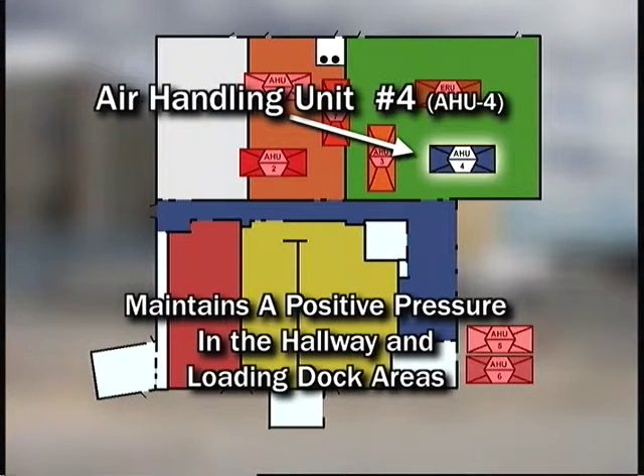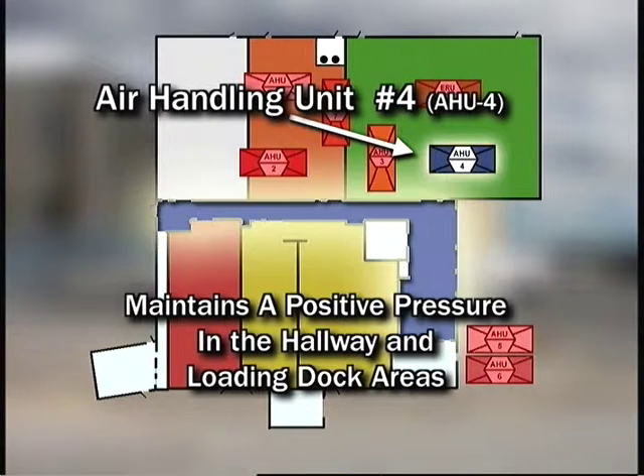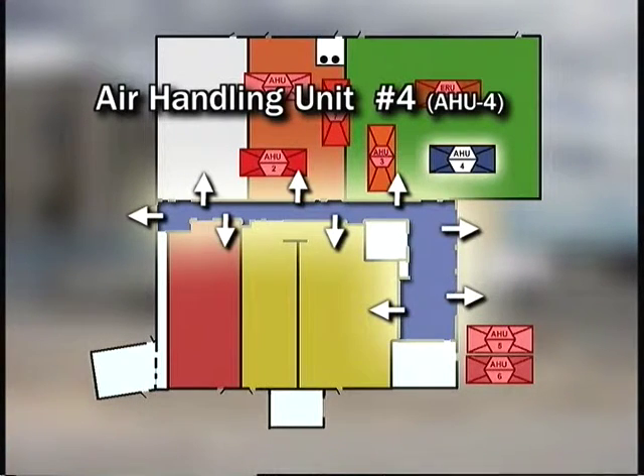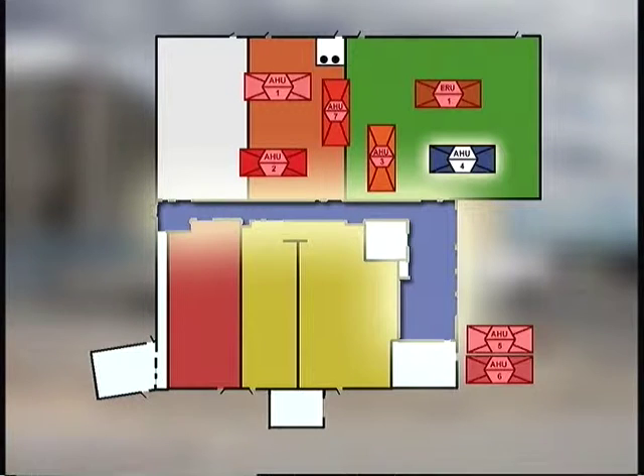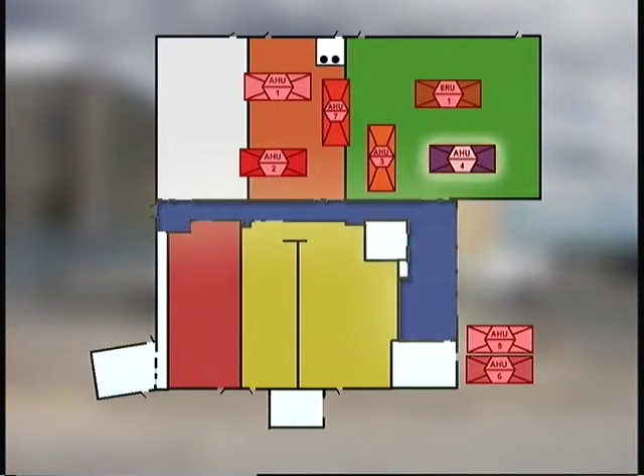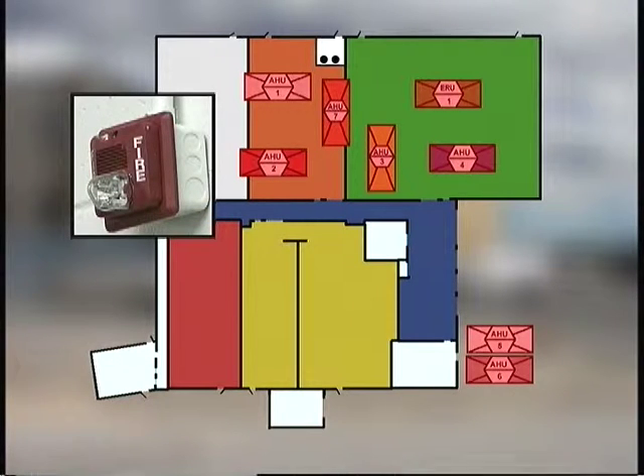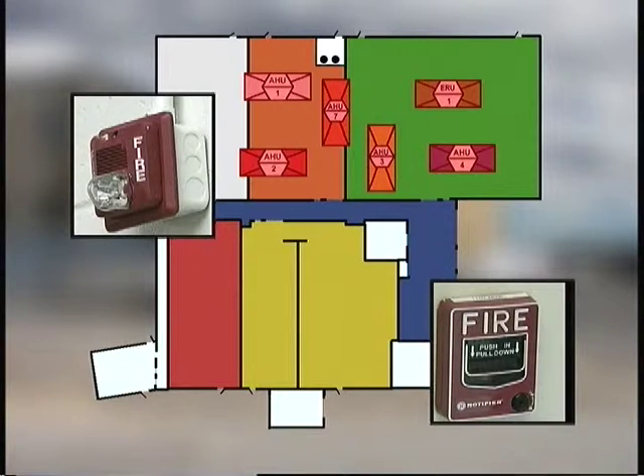Air handling unit AHU 4 will remain in operation to provide a positive pressure condition in the corridor and load dock area. This will keep smoke from a fire in any of the storage rooms from entering the corridor. In the event of a fire in the corridor or loading dock, air handling unit AHU 4 will shut down automatically. Upon a signal from any of these devices, horn strobe appliances located throughout the building will also activate. Fire alarm pull stations will also cause horn strobe devices to activate throughout the facility.